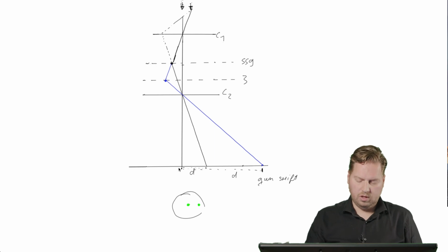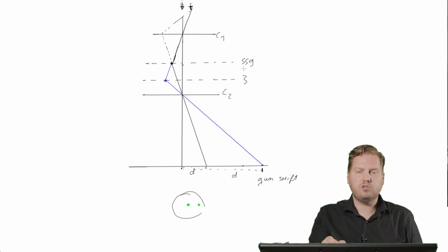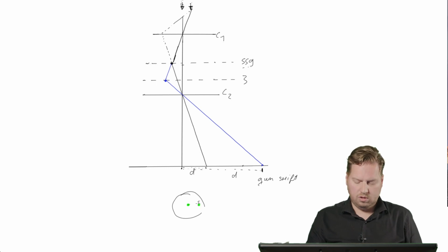Yeah? So you of course need to start from the middle. So what you can try in this routine is you can use a beam shift. So when you make the beam to a spot, you can use your beam shift to bring that spot to the center. So just easier for you. It doesn't do anything, but it's easier for you to see that we start from the center. And you do this with spot size 9. And then you switch to spot size 3. You'll see that the beam will move away from the center. And you activate your gun shift. And you then move with gun shift. You move that spot back to the center.